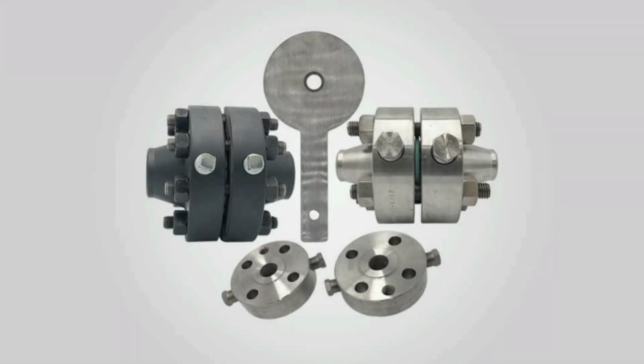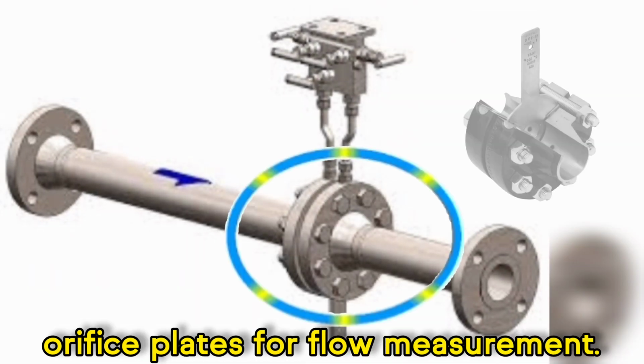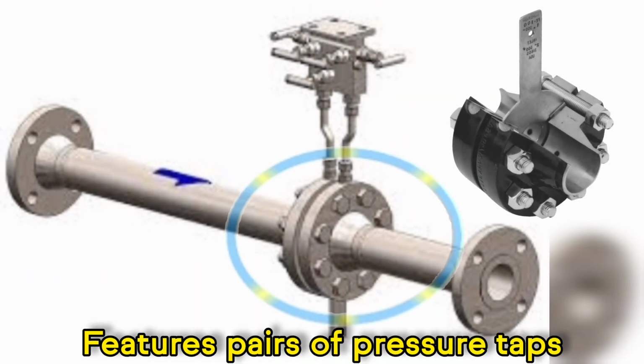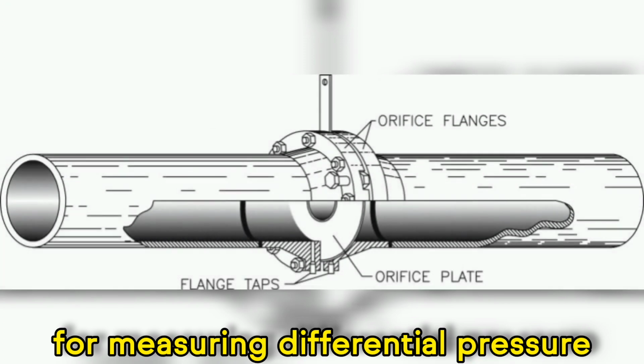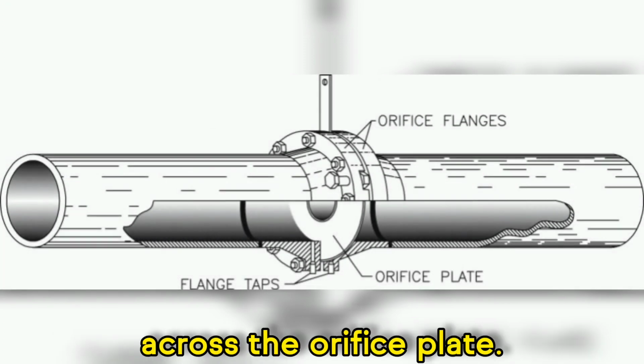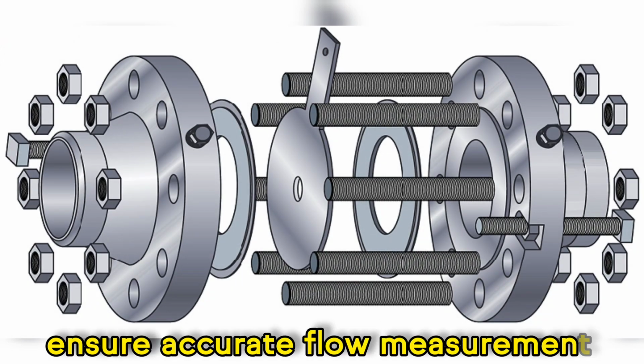Number 9. Orifice flange. Specifically designed to accommodate orifice plates for flow measurement. Features pairs of pressure taps for measuring differential pressure across the orifice plate. Requires precise alignment and installation to ensure accurate flow measurement.